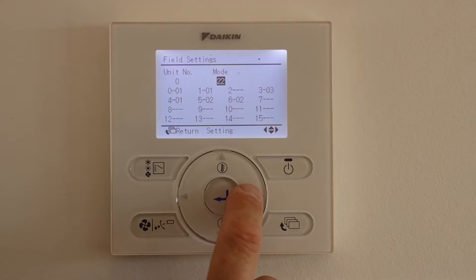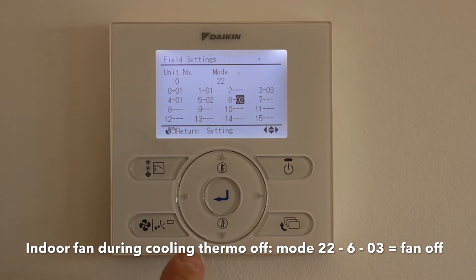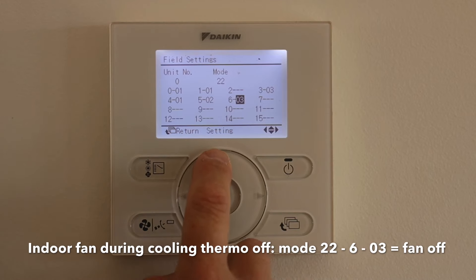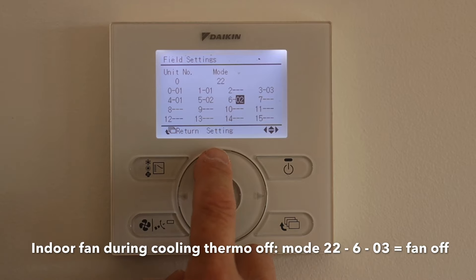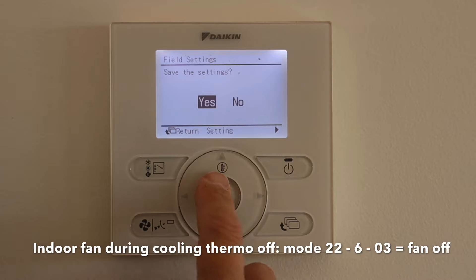The next one we want to set is 22-6-03, and that's for cooling — cycling the fan off. It's currently set to 02. Again you have 01, 02 and 03: 01 is low-low, 02 is set fan speed on the controller, and 03 is off. We want to set it to 03. Enter. Yes.